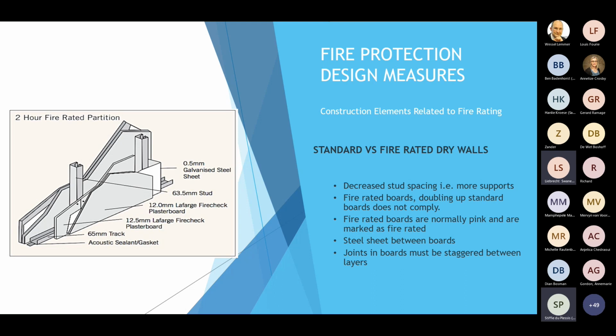Now, a problem, and it's only to take note of it, because it is problematic and it does happen in the industry. Each and every contractor, some know about it, some don't, are using your normal ceiling board, which is your white gray board. That board doesn't give you any fire rating at all. Then they use the pink board to install the panel, giving you a fire rating as required in the code of practice.